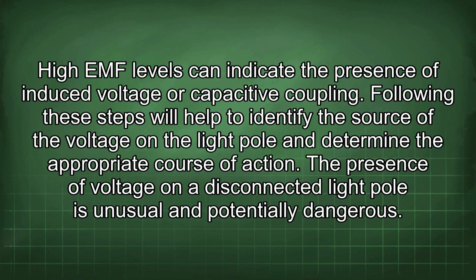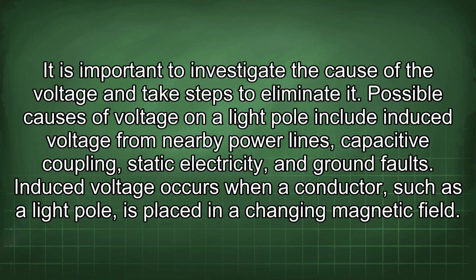Following these steps will help to identify the source of the voltage on the light pole and determine the appropriate course of action. The presence of voltage on a disconnected light pole is unusual and potentially dangerous. It is important to investigate the cause of the voltage and take steps to eliminate it. Possible causes of voltage on a light pole include induced voltage from nearby power lines, capacitive coupling, static electricity, and ground faults.